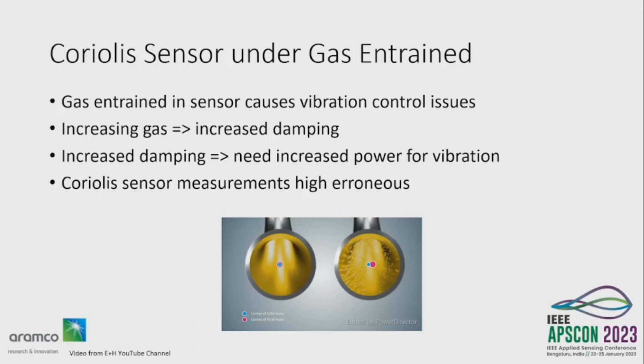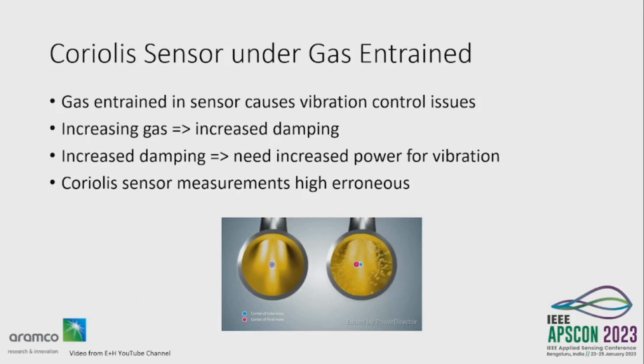So if you can play that video, it shows what's happening. The tube on the left has a pure fluid, so the center of mass of the fluid and the center of mass of the tube are coincident, so there's no problem. But when gas is entrained in the fluid, the gas is actually stationary while the tube and liquid move on either side. So the center of mass of the fluid is moving, but the center of mass of the tube isn't, so they're no longer coincident. That's what causes the errors in the meter.